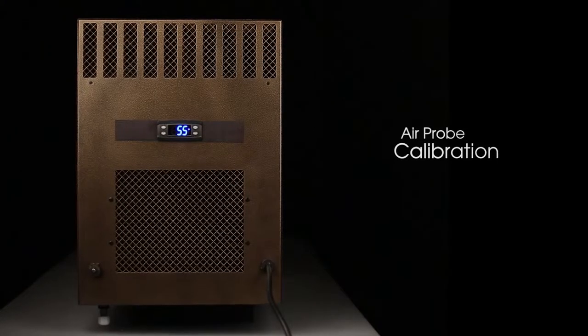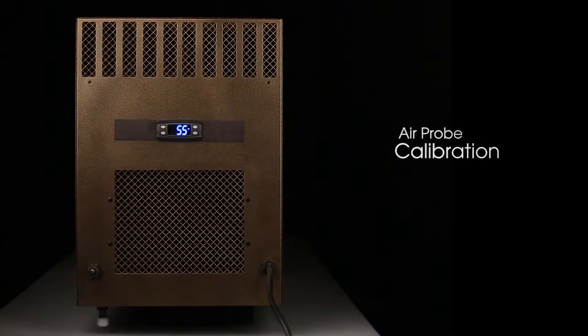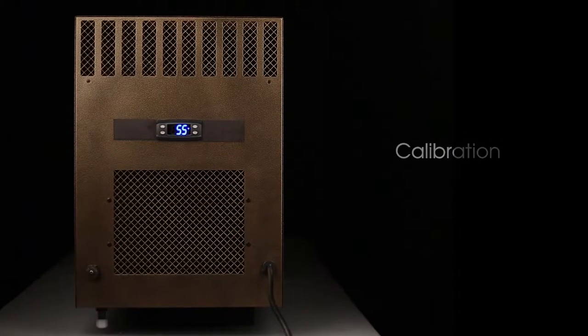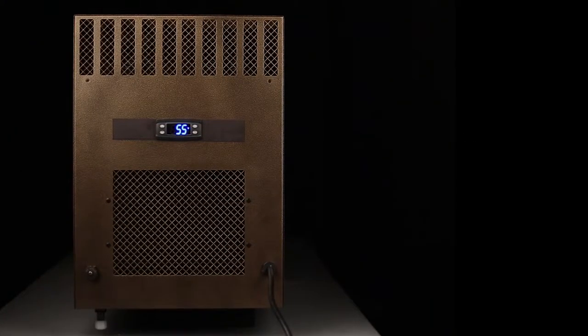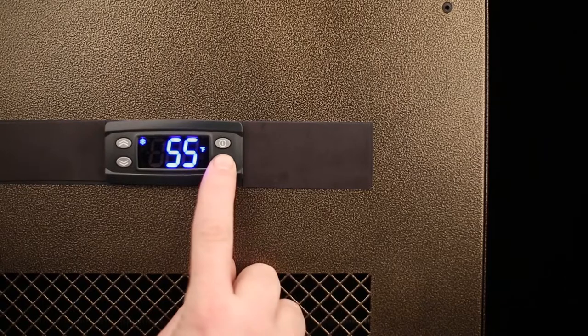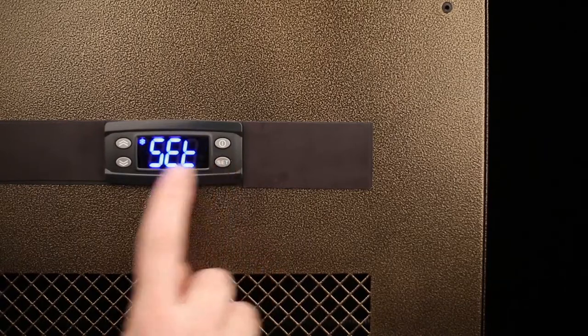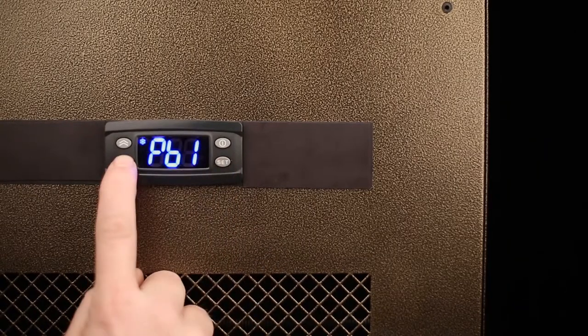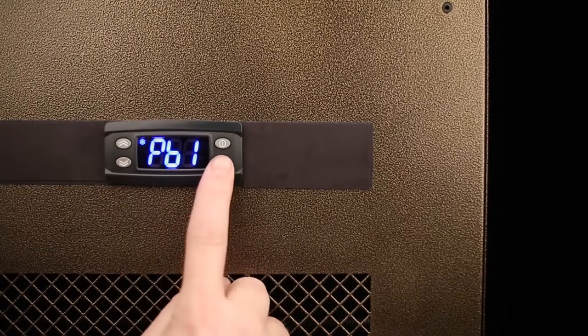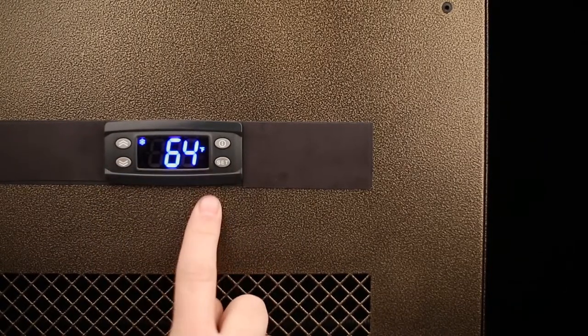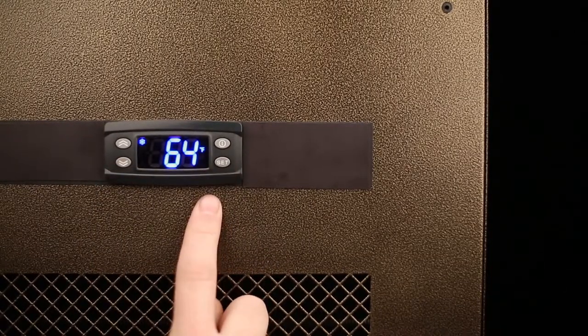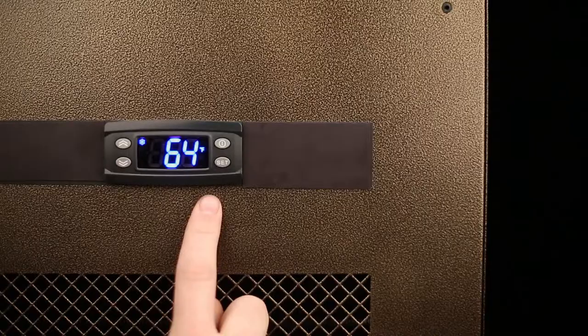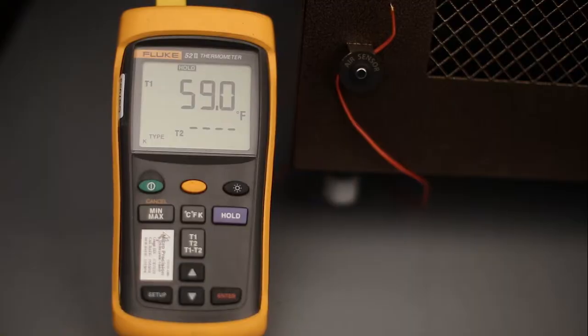To calibrate the air probe, first check the temperature of the probe. Press the set button once, scroll down to the PB1 menu, and press the set button again. This will show you the temperature the sensor is reading now.